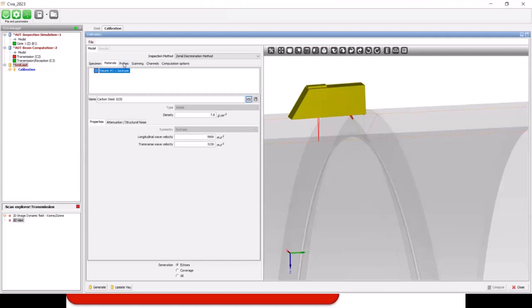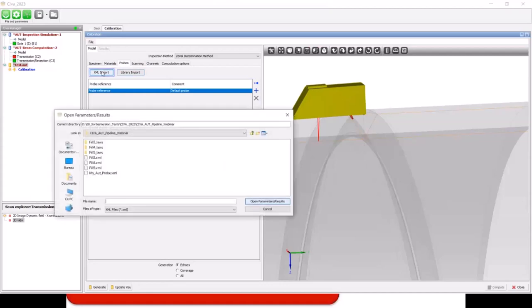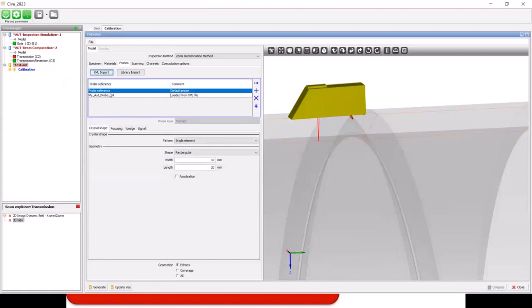For probes, you can load from the library or from a probe you defined in CIVA before, through an XML import. I'll load the AUT probe I defined in the previous demo. You can have a list of probes available for the project — useful if your system uses a set of different probes. In this case I'll keep just the one AUT probe: 4 MHz, matching what was simulated in the other module.